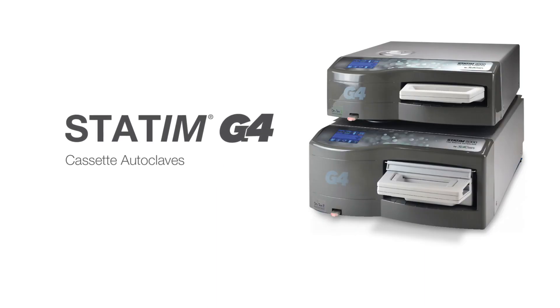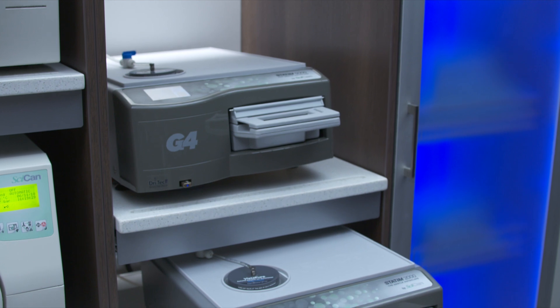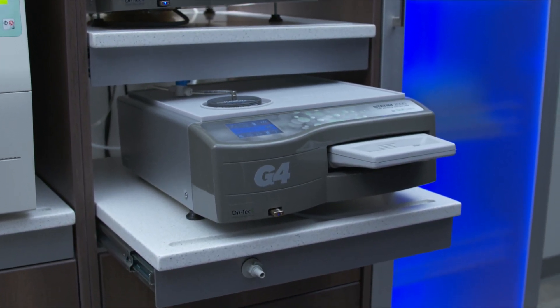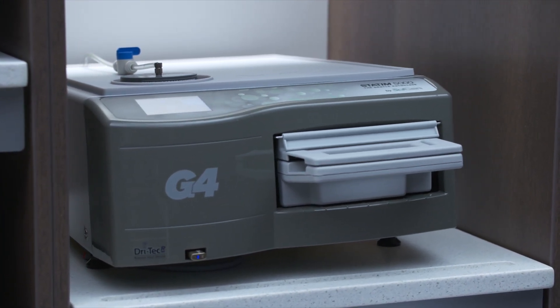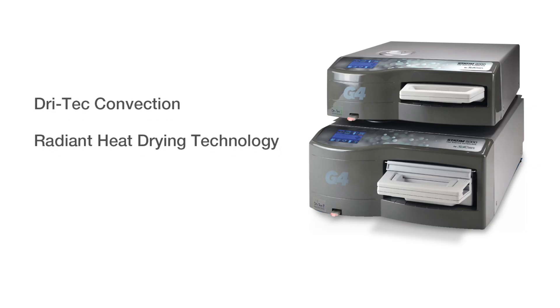Congratulations on your purchase of the STATIM G4. The STATIM G4 is an innovative tabletop cassette autoclave that uses dynamic air removal technology, also known as steam flush pressure pulse technology, to remove air and effectively sterilize instruments. Not only does the STATIM G4 unit have rapid sterilization, but with the Dri-Tec convection and radiant heat drying technology, it also enables rapid drying.